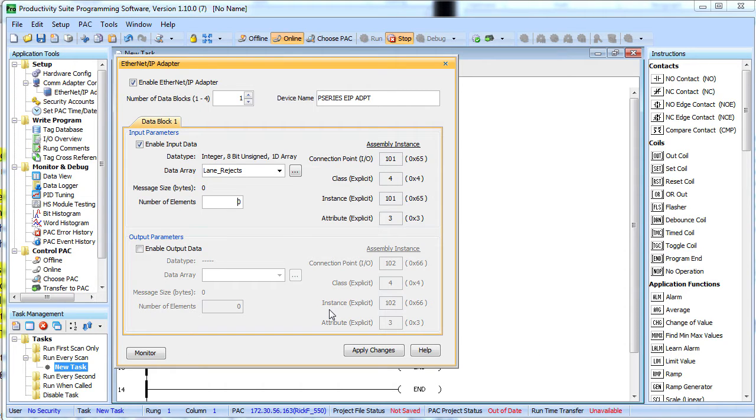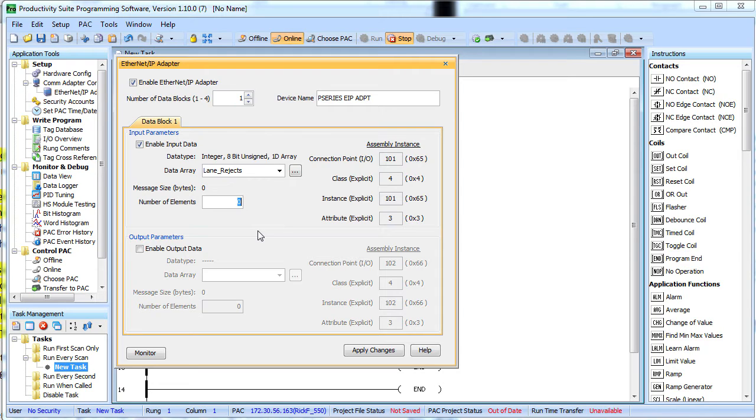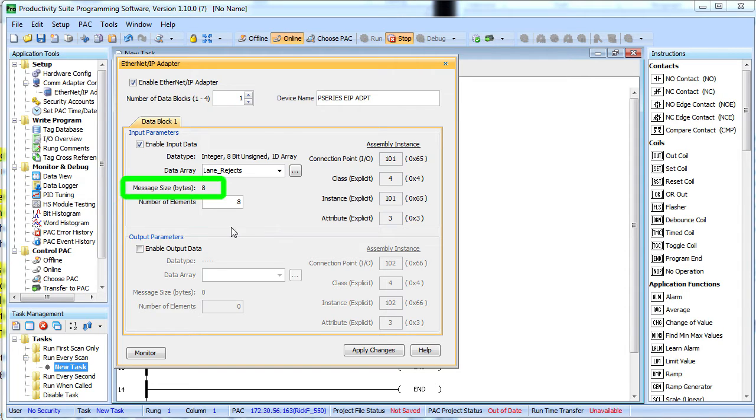Great. My 32 lane data array is defined, well guess what, down here in this box I can limit how much of that data is exposed to the scanner. I only have 8 lanes running today, so I'm just going to put an 8 there that will limit the amount of data that is sent back to the scanner to just those 8 bytes. So you can see that here.